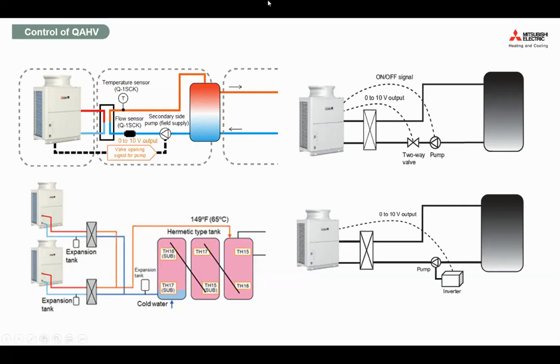However, like I mentioned before, you can join up to 16 of these units to create a bigger system. Because it comes with an internal pump, we strongly recommend having each individual heat exchanger service each load. I mean each QAHV. Just make sure the load is not being disturbed, and the unit will self-regulate depending on the load requirement and the ambient condition. The unit will make the decision on which unit to turn on and at what capacity, based on its own algorithm, to accommodate what's required on your hot water requirement side.